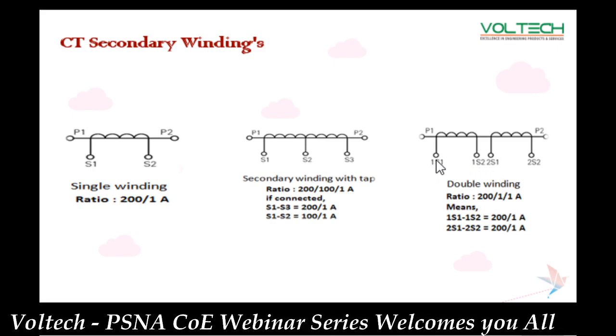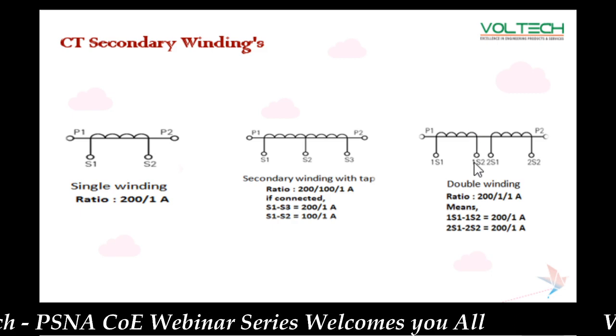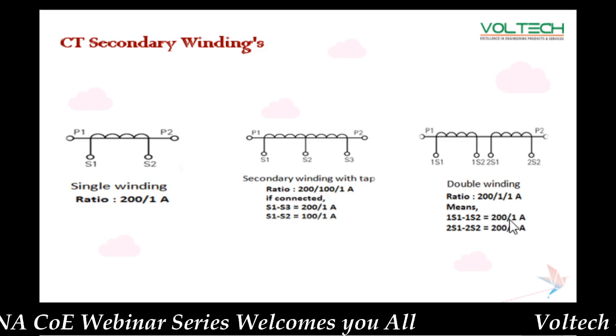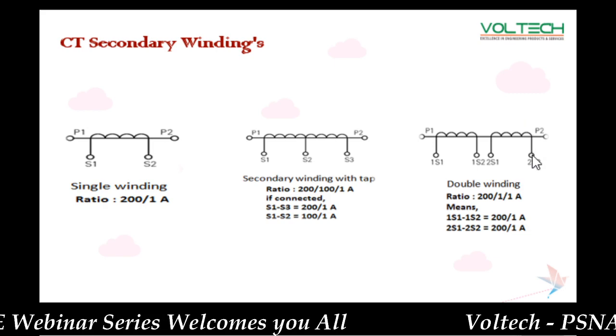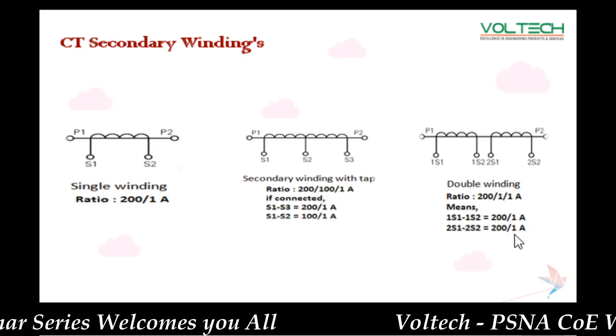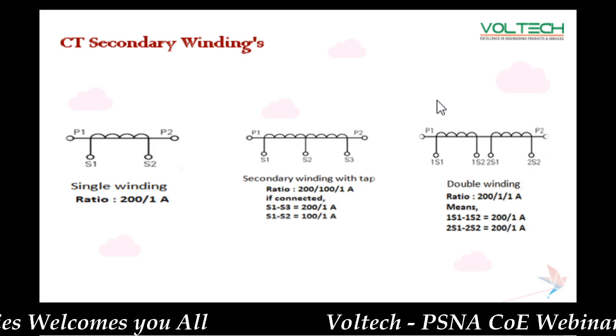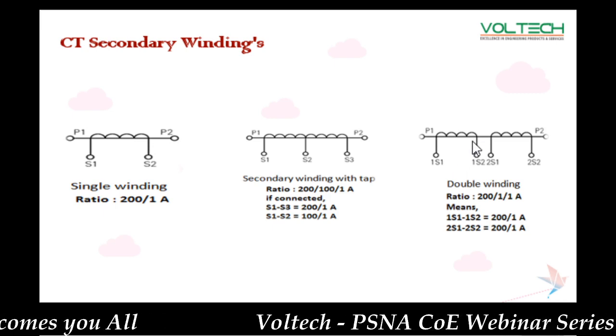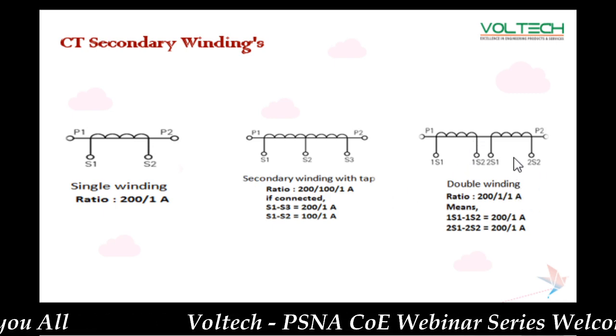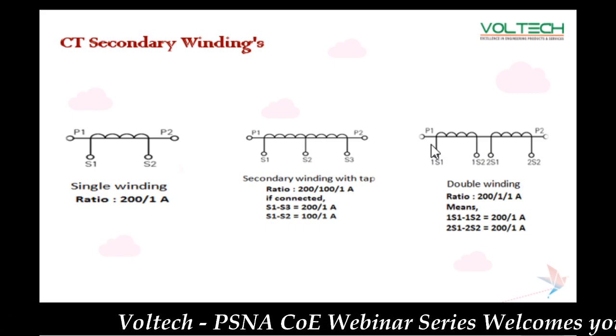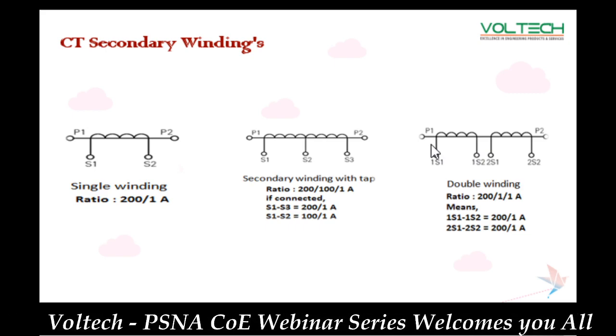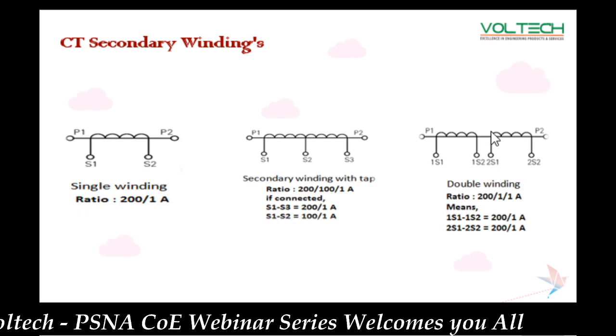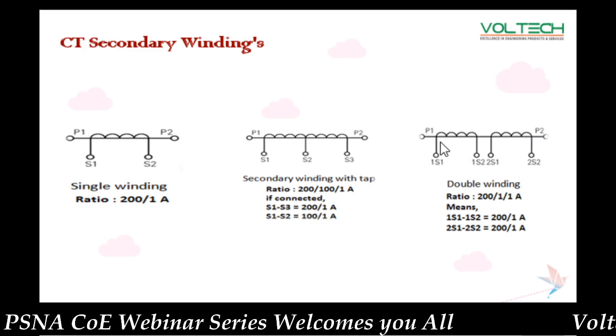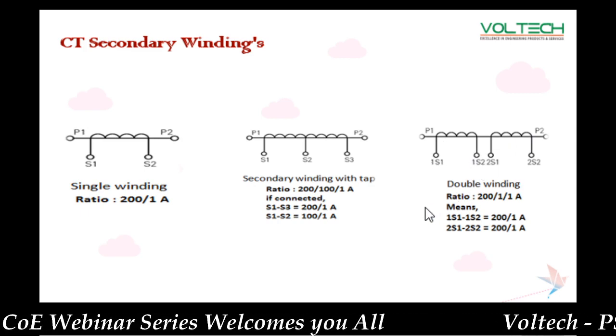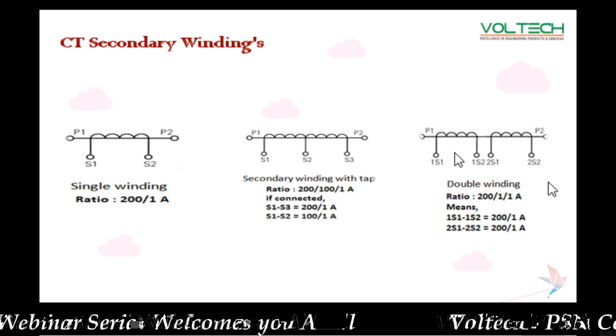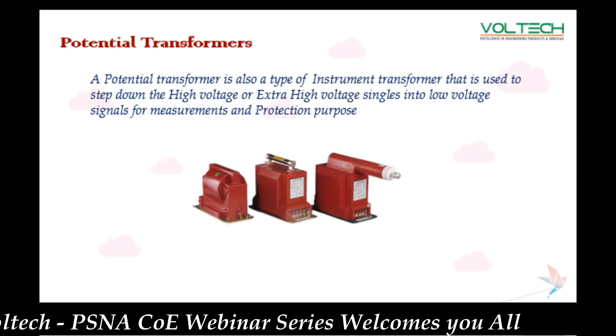So here 1S1, 1S2 gives the ratio of 200 by 1. The same with 2S1, 2S2, giving the same ratio. So it depends upon our application. That means one is for metering, one is for protection, or if you want remote measurements or remote monitoring, we can add the windings. So we can specify the winding for the type of application: one for protection and one for monitoring.